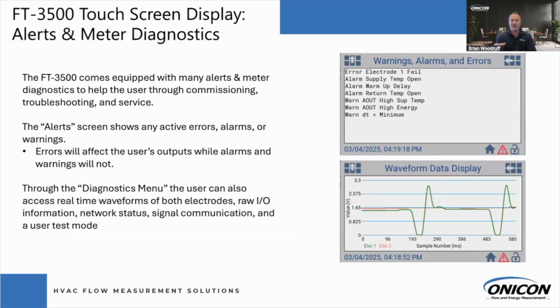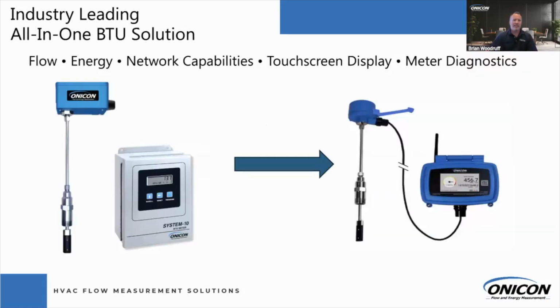As well as, if you notice there on the right, the waveform. So that's awesome because you're able to see electrode 1 versus electrode 2 and able to see when the signal's coming in, when it's going out, and if both of them are reading or if one of them is not. So we're really able to dive in without having you send the meter back for repair every single time. Then you're out roughly 2 weeks. We're able to handle a lot of this on site with someone just in front of that display. Next, I'll turn it back over to Mike to talk about the BTU options.